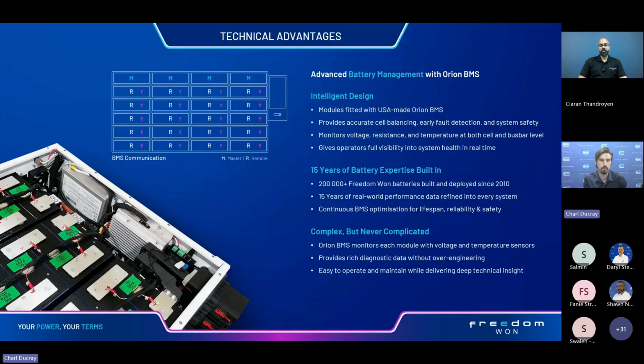So something really cool about the megaTower is that we've stuck with the Orion BMS. This is one of the known secrets to Freedom Won success, that we've got an American-made BMS that we've developed for over 14 years with Orion. And that's been a critical factor in ensuring that our battery's performance is optimal and that we can back what we've guaranteed on our warranty. Our co-development with Orion on this BMS ensures that it's made per our requirements for exactly what we want. We have the master BMS, as you can see on the top row. So it's only the top modules that have the master BMS, and all the intermediate and bottom modules have the remote BMSs. The remote BMSs communicate back up to the master all their cell voltages and internal temperatures, which are measured by inbuilt temperature probes.